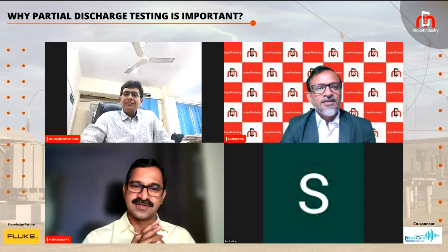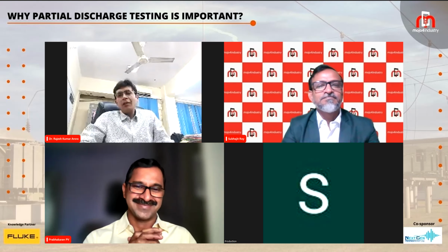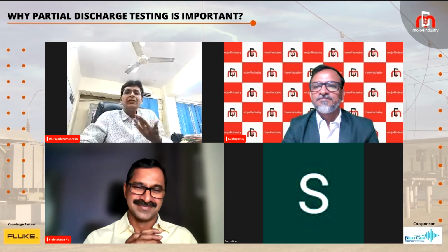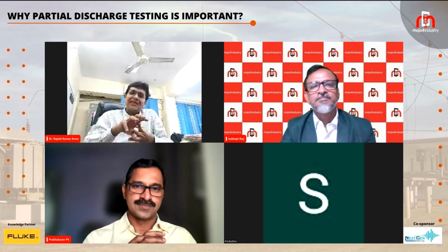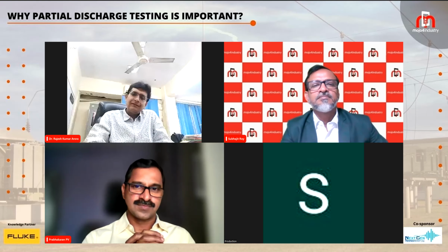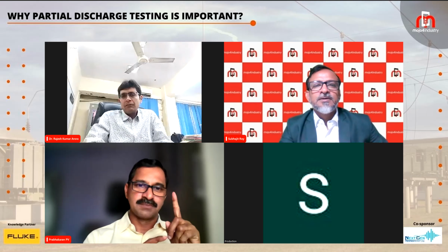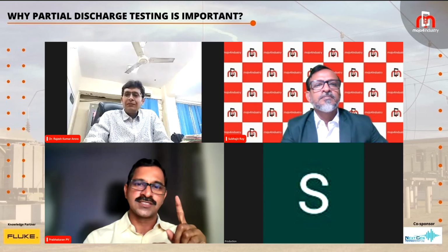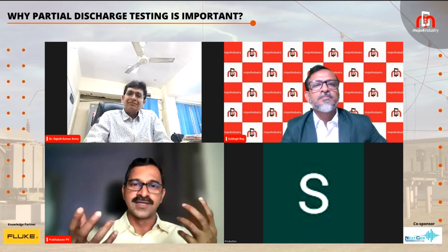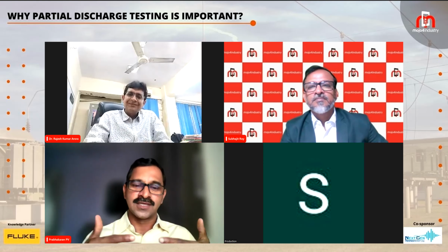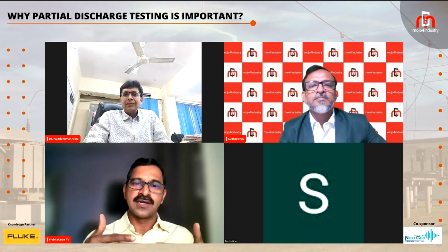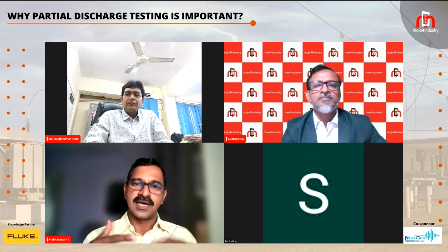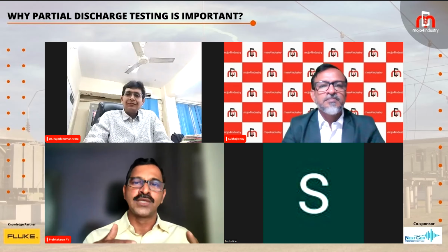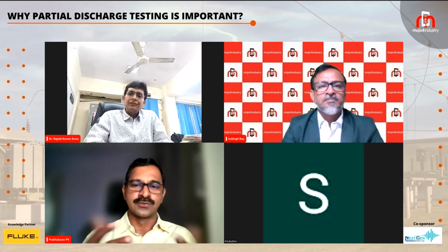Is there any threshold limit for partial discharge? It depends on the partial discharge we are getting. For every partial discharge, there's some pattern, and based on that pattern we can identify the quantum of imperfection of insulation and the action to be taken accordingly. Majority of engineers may not be aware of how to analyze and read the PRPD, but expert committee members can help interpret it easily, and that makes a difference.